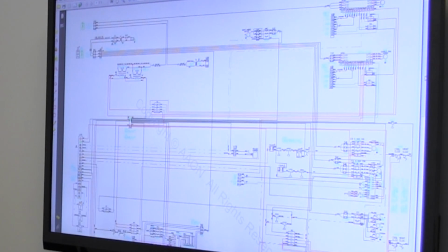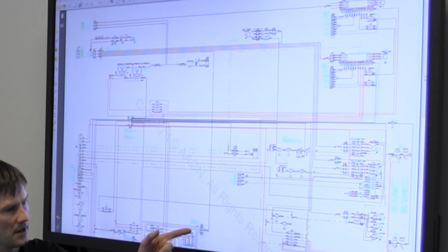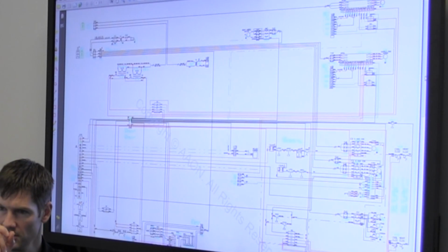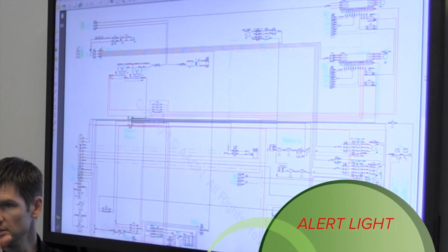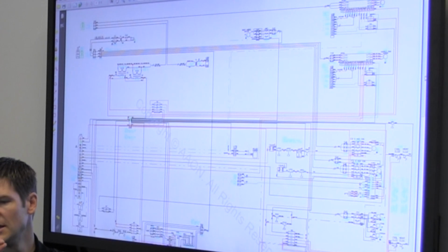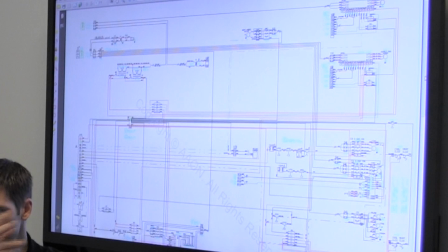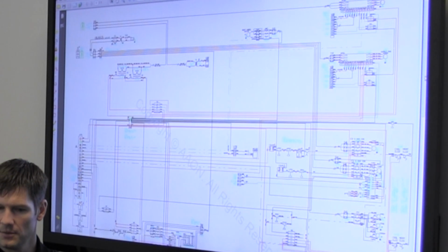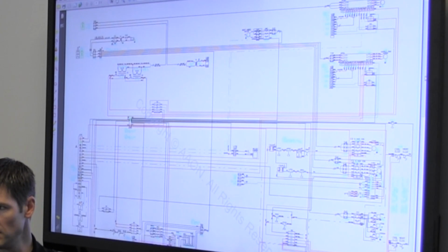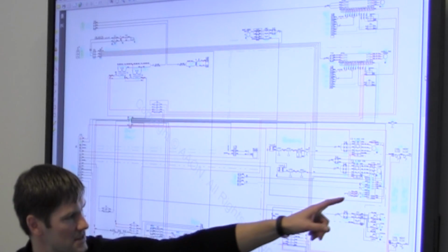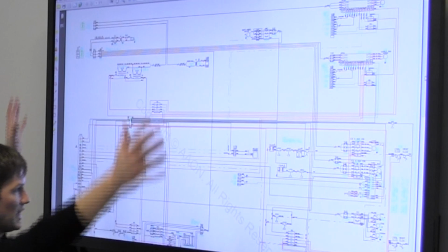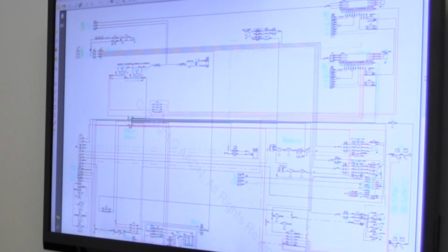compressor. One thing to note on that black box, everybody at some point goes up to one of these units, sees that black box, the compressor's not running, and they see the little red light blinking. And it says alert. It doesn't say alarm, but it says alert. And there's 9 different codes. If it blinks 9 times, it means this. If it blinks 2 times, it means this. Those are all alerts or warnings. They're not necessarily alarms.